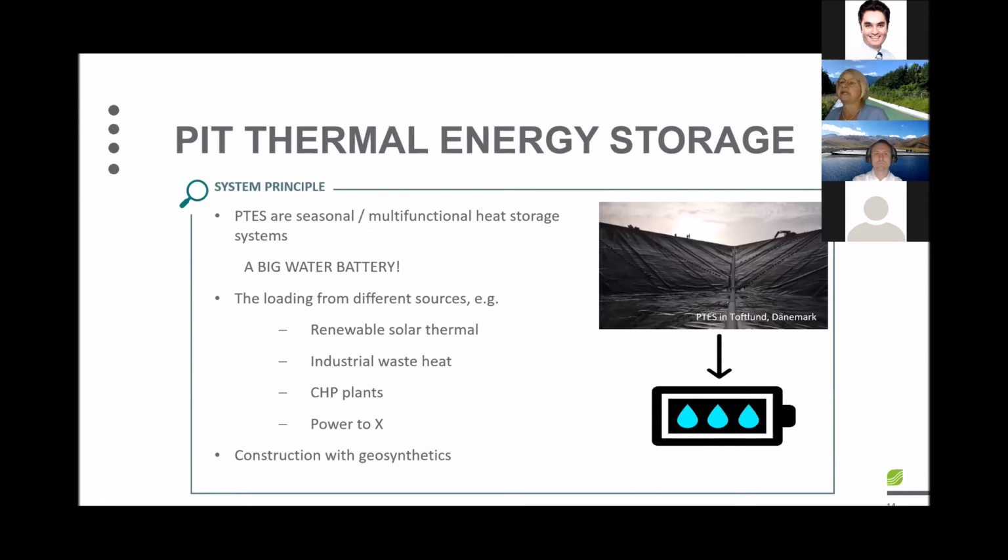So what is a PTES? It is a seasonal or multifunctional heat storage system, and it's a big water battery in principle. Seasonal means that we have one loading and unloading per season, and multifunctional means that there are multiple loadings and unloadings per season. As I said already at the beginning, the loading comes from different energy sources like renewable solar thermal energy, or even industrial waste heat, or we can have combined heat power plants, for example. The construction is done with geosynthetics.